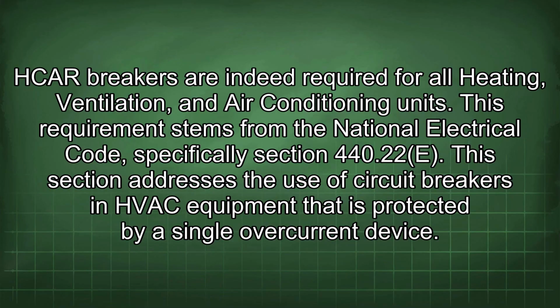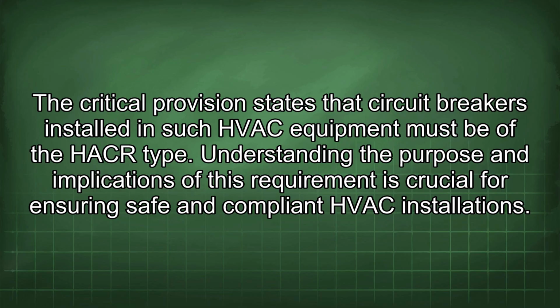HACR breakers are indeed required for all heating, ventilation, and air conditioning units. This requirement stems from the National Electrical Code, specifically Section 440.22(E). This section addresses the use of circuit breakers in HVAC equipment that is protected by a single overcurrent device. The critical provision states that circuit breakers installed in such HVAC equipment must be of the HACR type. Understanding the purpose and implications of this requirement is crucial for ensuring safe and compliant HVAC installations.